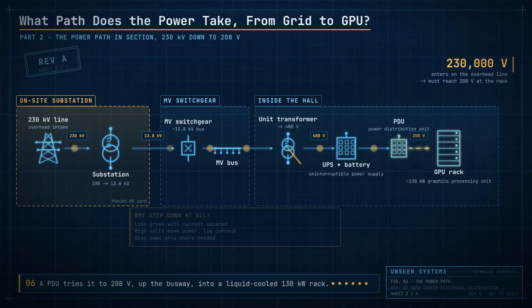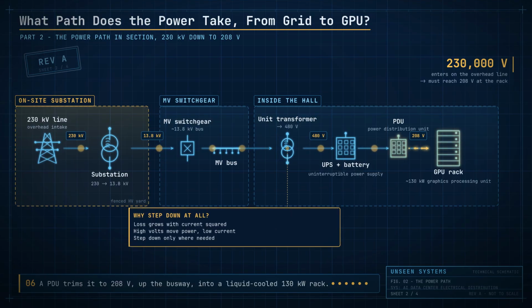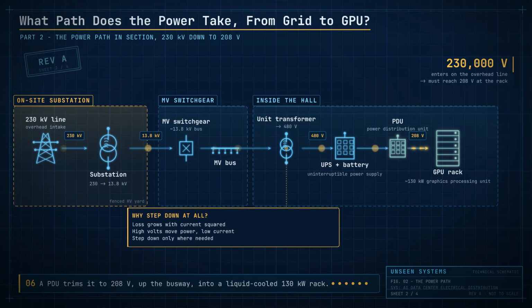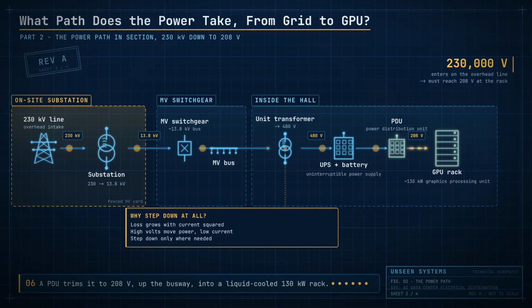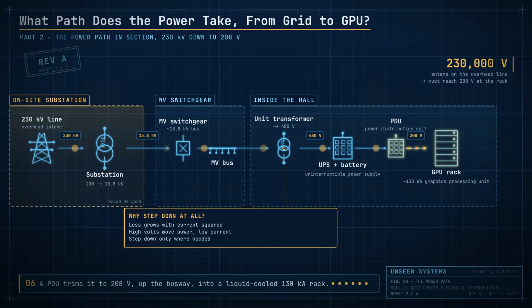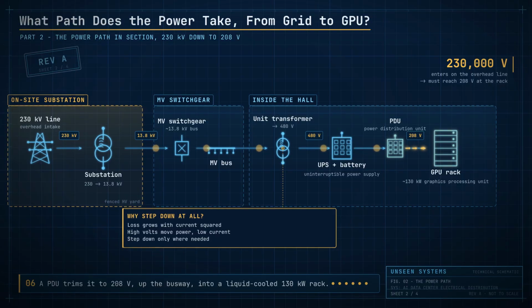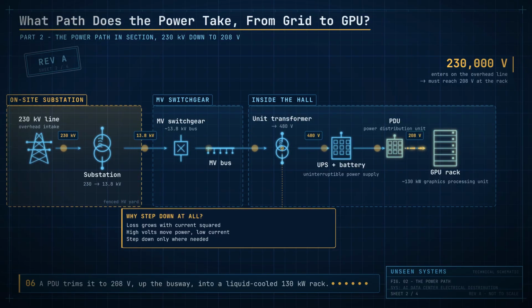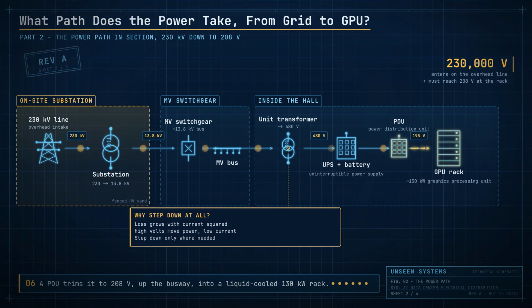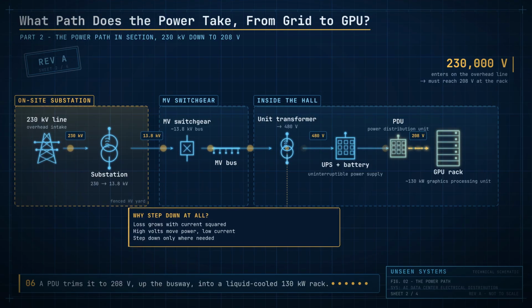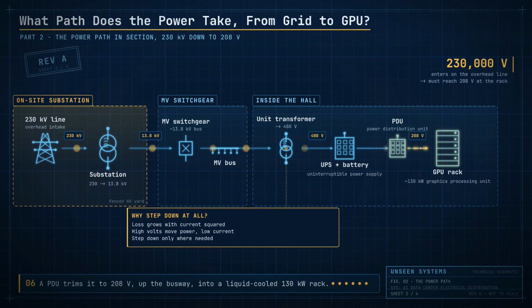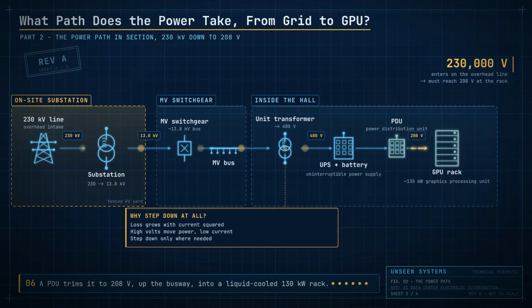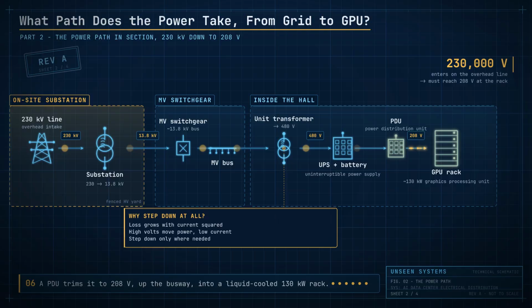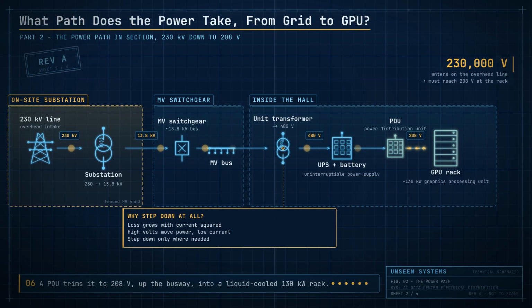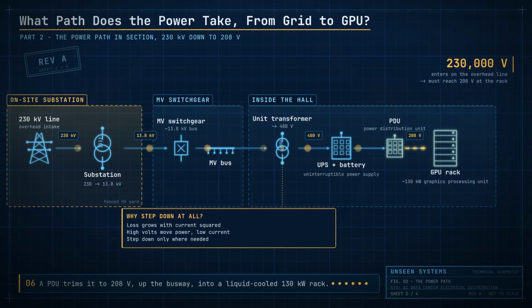From there, a power distribution unit, a PDU, makes the final step down to 208 volts and hands it to a busway, an overhead bus bar running above the aisle that carries it the last few meters straight over the tops of the racks. And at the end of that busway sits the rack itself, about 130 kilowatts in a single cabinet, running so hot the whole thing has to be liquid-cooled. That is the end of the line, transmission tower to GPU, one continuous copper path, stepped down 3 times along the way.